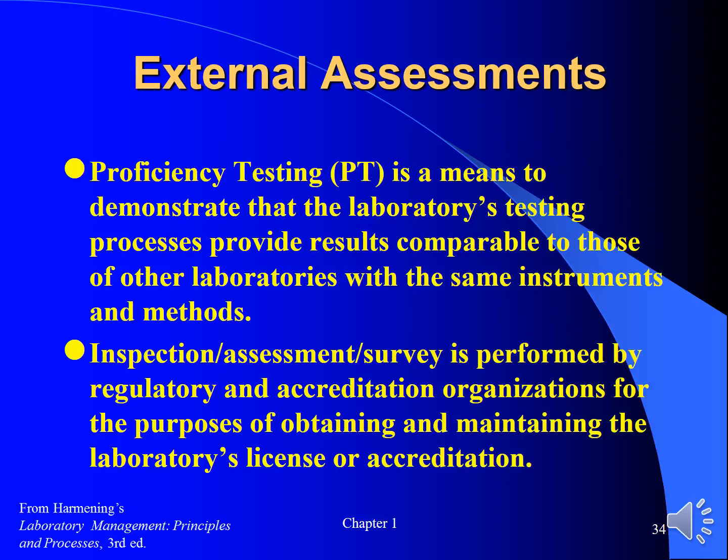There are two types of external assessments: proficiency testing, or PT, and inspection, or assessment, or survey. In PT, the laboratory receives samples for testing from a designated PT provider and performs the testing using its routine processes, procedures, and staff. Results are compared to those of the PT provider and the other laboratories, and the laboratory gets a report of its performance.